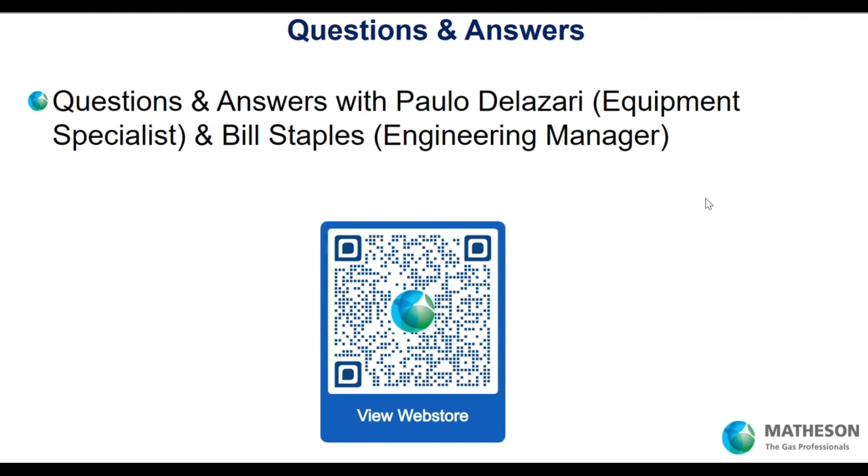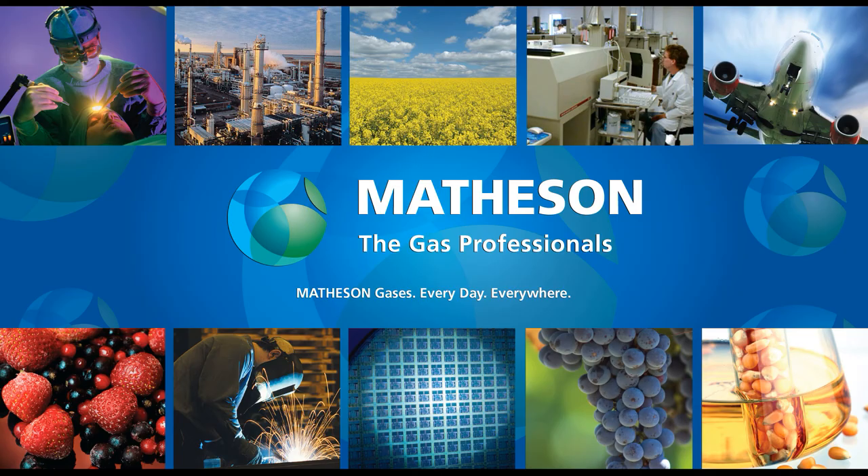We mentioned at the beginning we'd have questions and answers starting with pre-submitted questions. If you don't see your question covered, submit it using the GoToMeeting toolbar. Paolo, go ahead and begin with our pre-event questions. The first question from Bob is: what is the reason for multiple floats within the same flow tube, and how do I know which one to read? Many of our FM 1050 rotameters have both a glass and stainless steel float to extend the range of the rotameter. You read the glass float until it goes to the top of the scale, and then you read the stainless steel float.